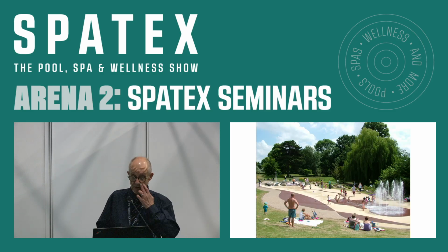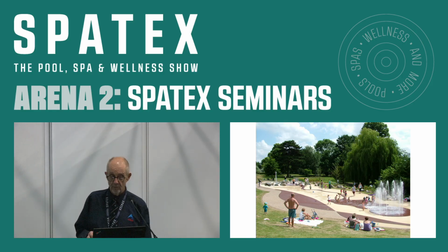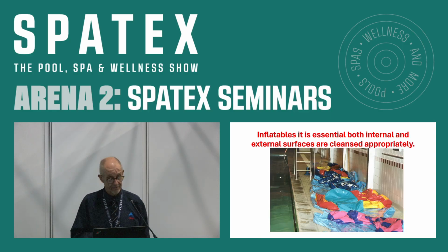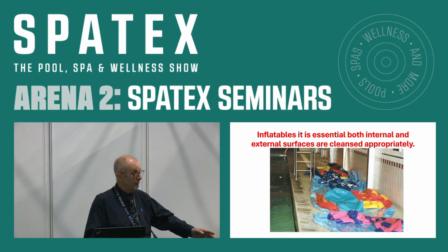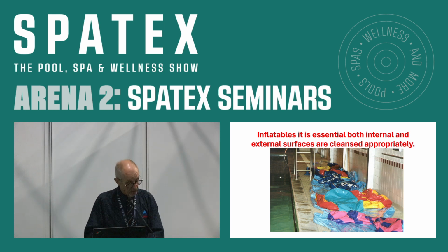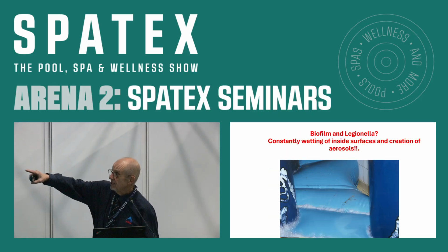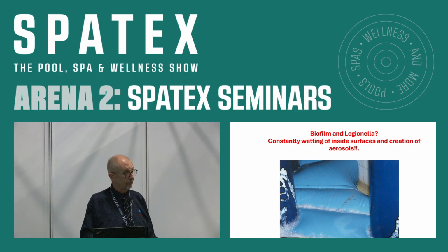Interactive water features, you can see those sprays there, and the water's blowing down away from those sprays. All those people could possibly be infected. Hydrotherapy pools and pools in general. This is very interesting. You should have a clear cleansing protocol for inflatables. As I said before, inside and outside. Why inside? Because they should be designed with a big zip on the bottom so you can expose the inner surfaces and cleanse them. Why? You can see here, if you look carefully, coming out of the seams there is an aerosol spray. So that's perfect for biofilm to grow within there and to be blown out.